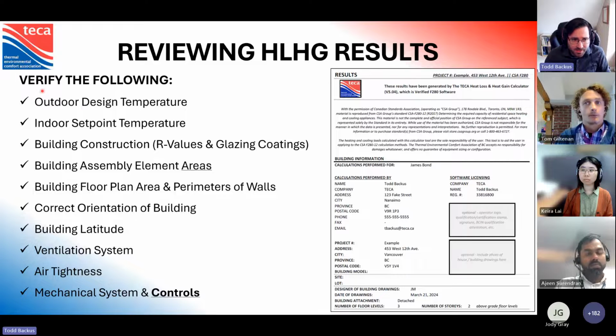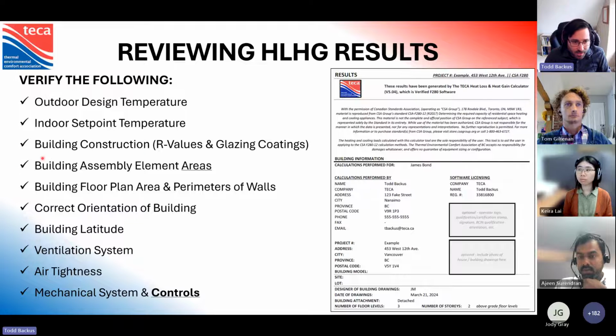So the outdoor design temperature and the indoor set point temperature, those are critical because that factors into your delta T that we've discussed a few times here. And that will impact every single calculation in the program. So if those are wrong, you end up being way off. Look at the building construction and the assembly areas. This is harder to look at. That's buried within the model, but you can look at the floor plan areas and just see, does that make sense with the perimeters of the walls?